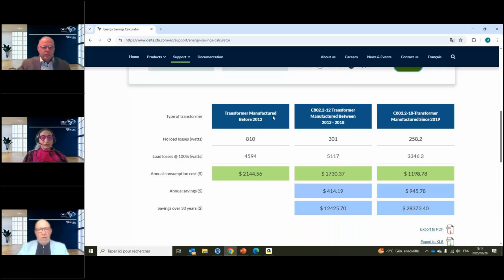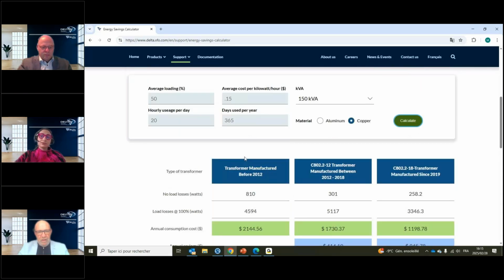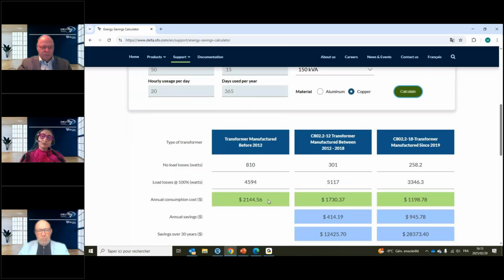The first column here is for transformers built before 2012. Most of the time, every 6 to 7 years we have changes and we have to meet more efficiency. Before 2012 there was an efficiency standard set back in 2006. We could go back further down the road, but let's just say before 2012. So there are the losses in your core, the no load losses, and your load losses in the winding. Based on your input data, your annual cost of the energy lost in that transformer is over $2,000. For the same type of transformer built between 2012 and 2019, you go down to $1,700. So you save about $400 a year.